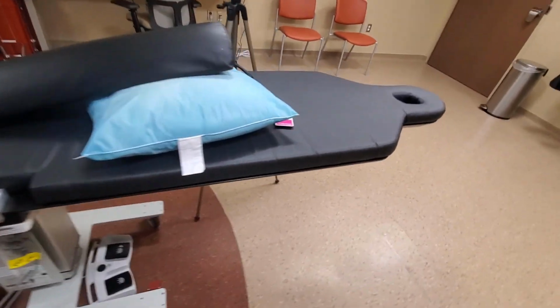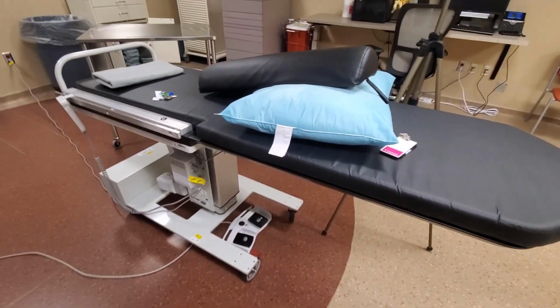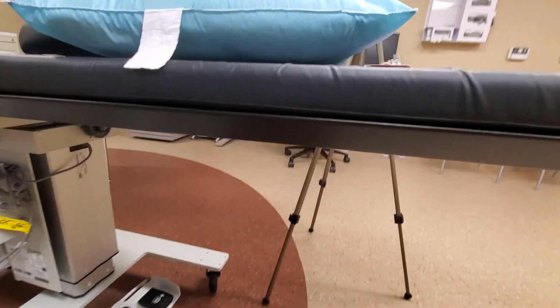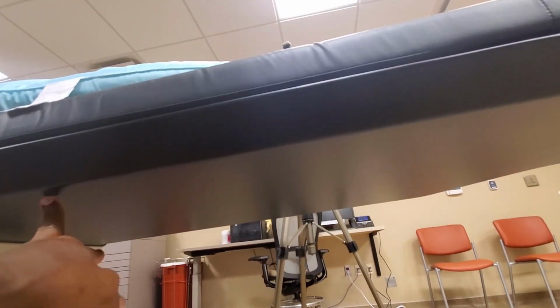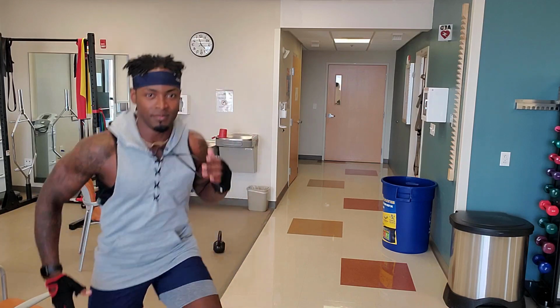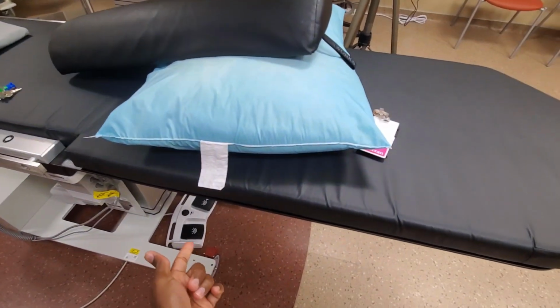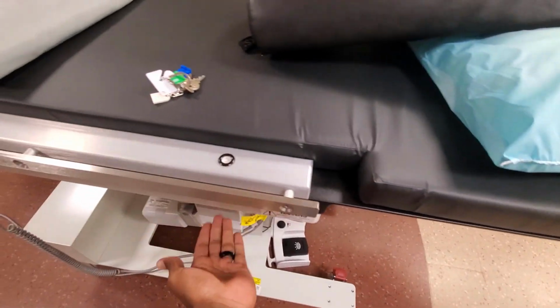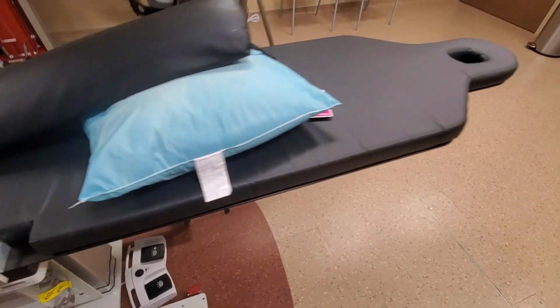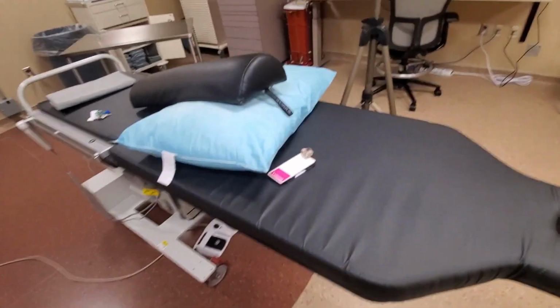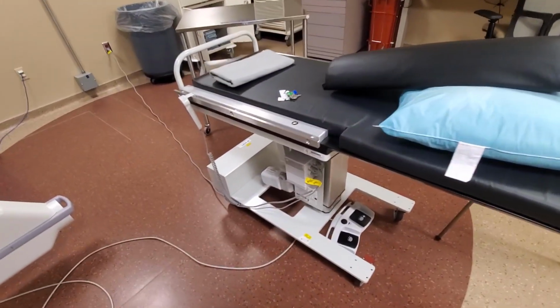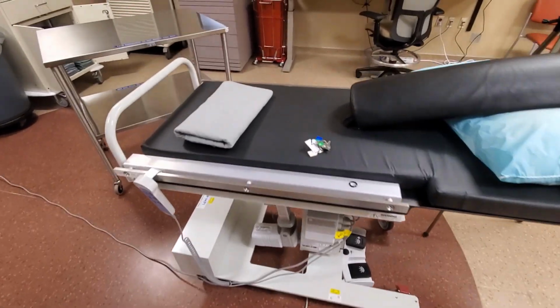All right, let's come over here to the table. The thing that's important for an IR table is that you want it to be radiolucent. You don't want it to have metal bars coming through here. You want the x-rays to go through here and out here, so this can go in between so we can see the patients. A lot of the tables have metal on them, and when there's metal on it, it's trying to penetrate this and the images won't come out. So that's one important thing to have with an IR table.